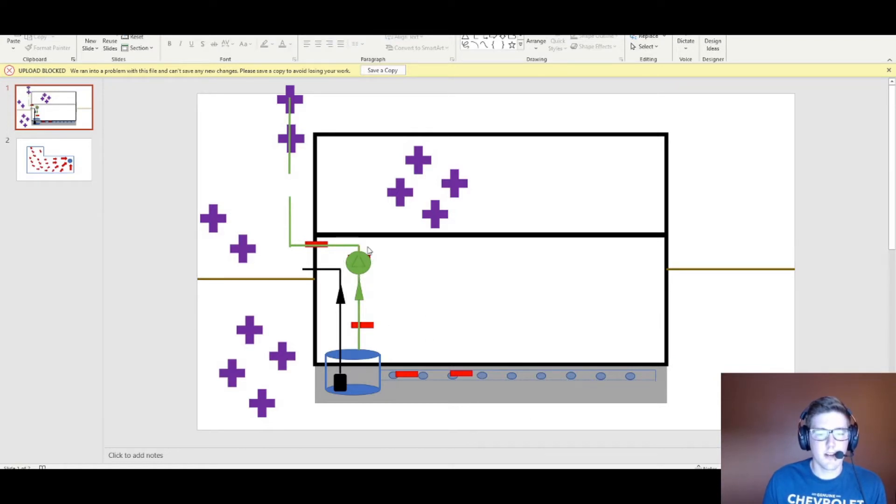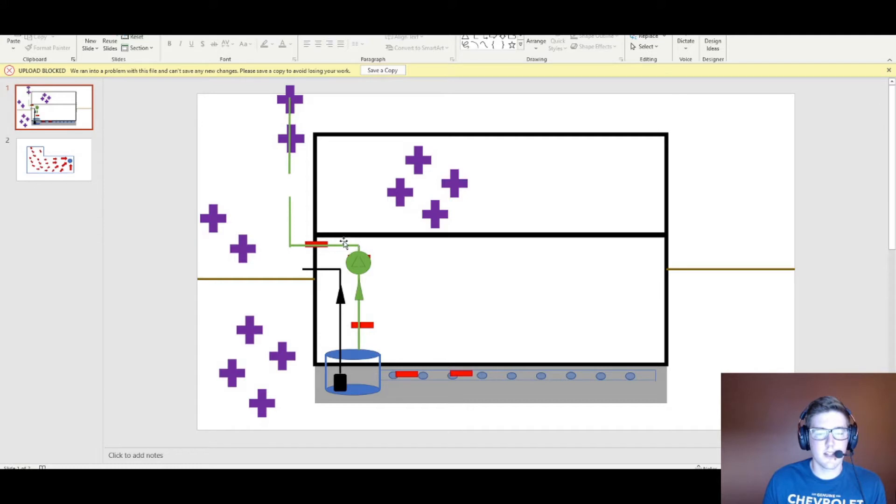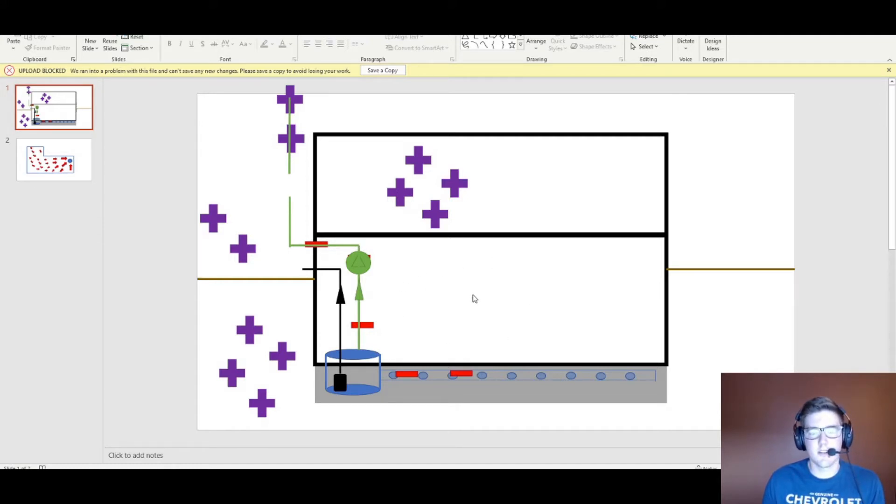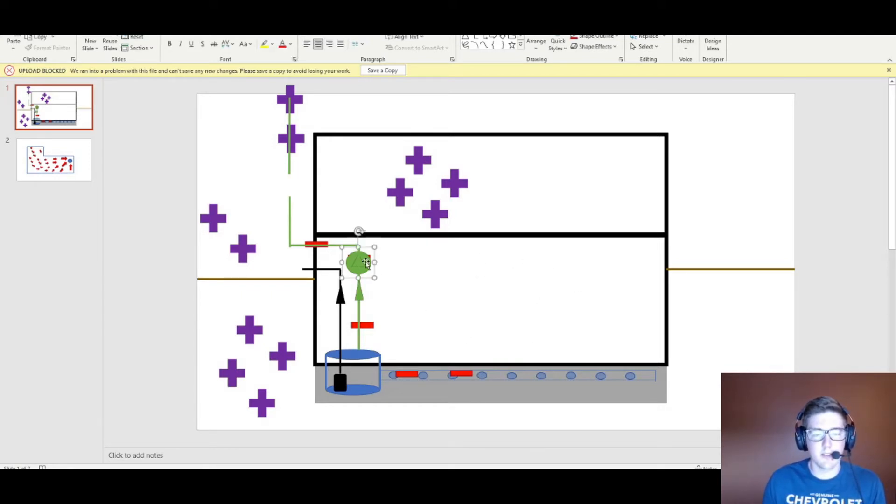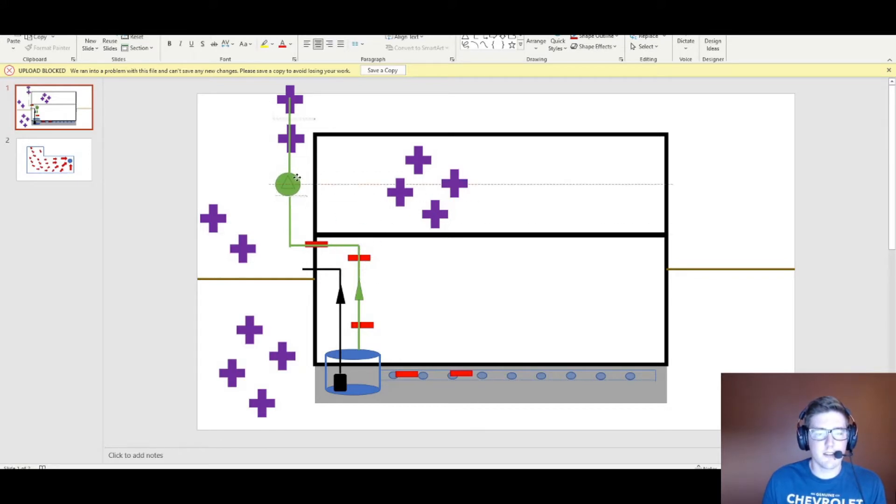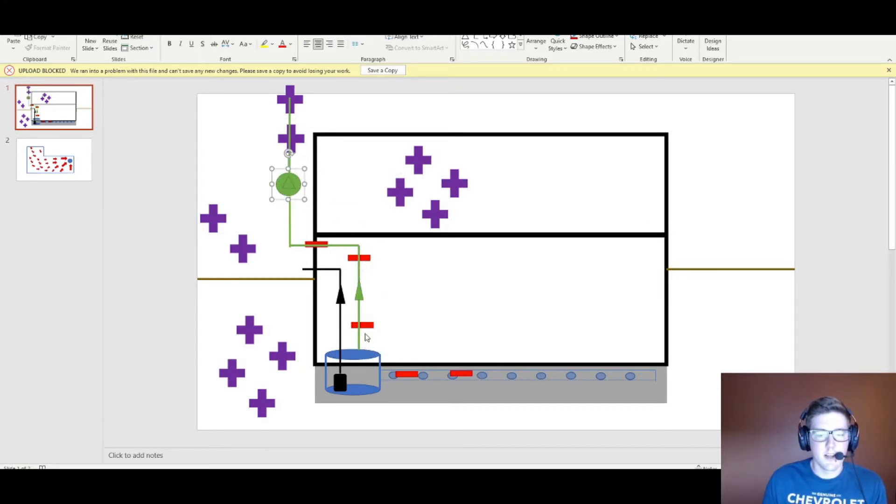If that discharge side is inside your house you could really ramp up the concentrations of radon and subterranean gases inside your house, which probably wouldn't be the best idea for you. So make sure that fan's outside, and when it's outside all you have is the suction side inside your house.